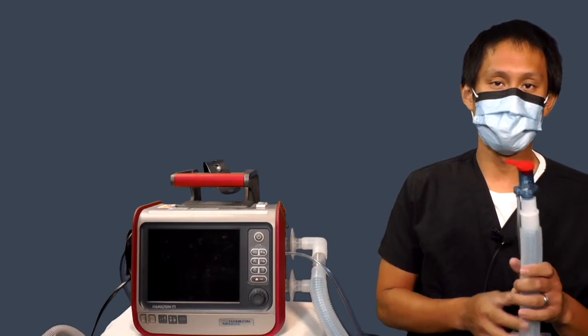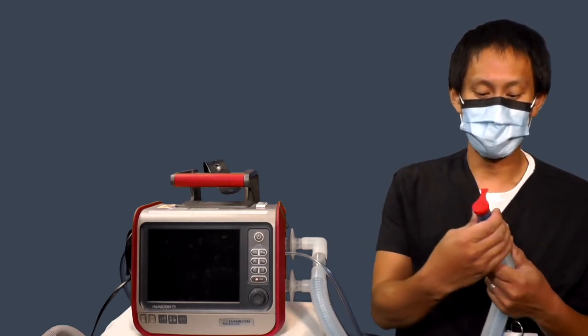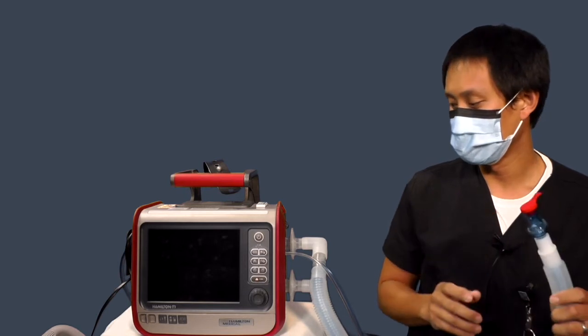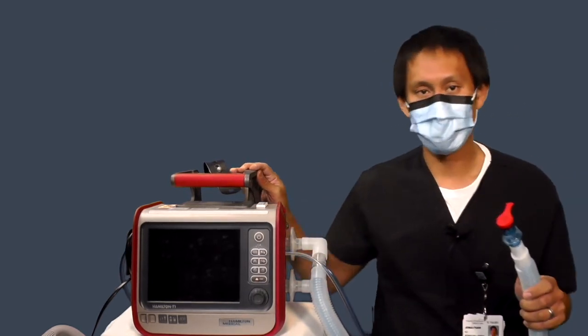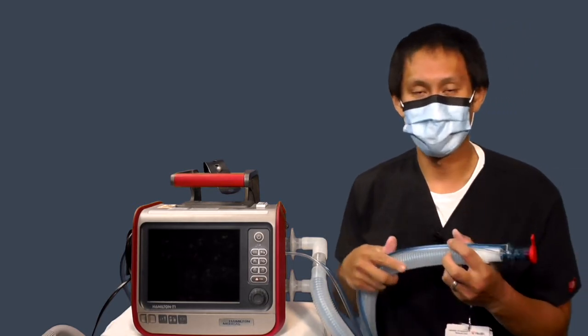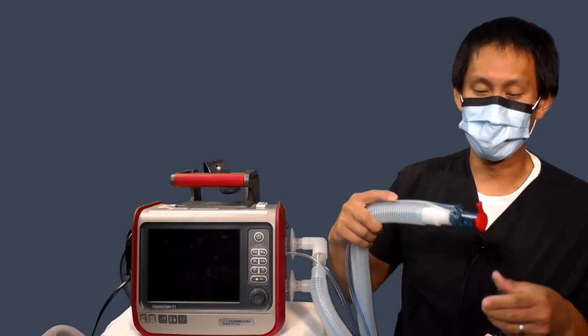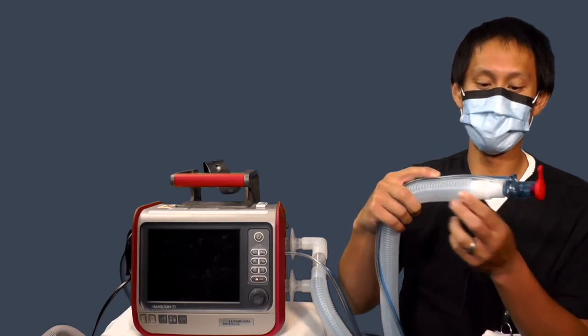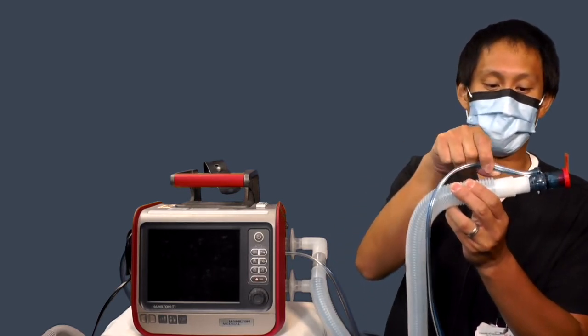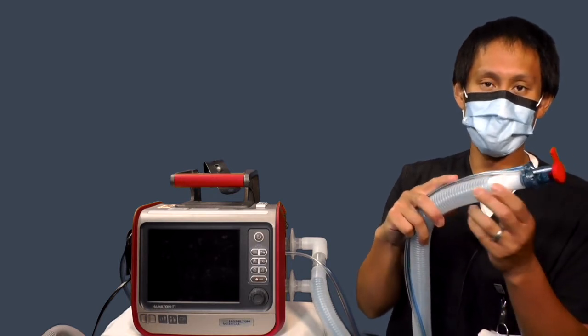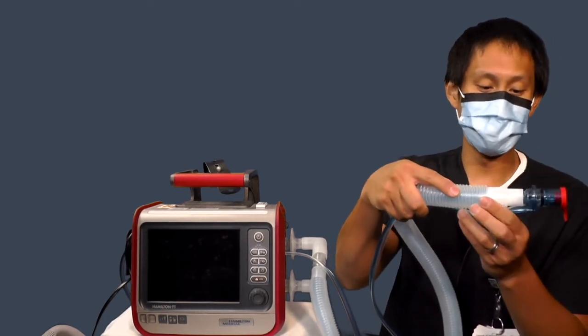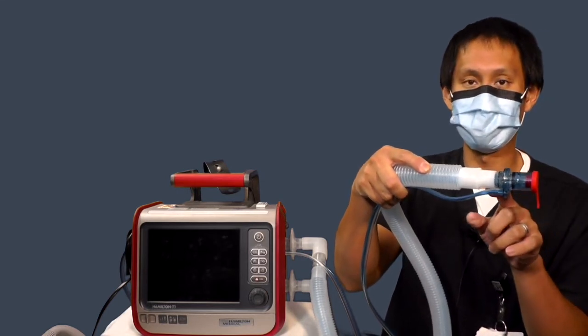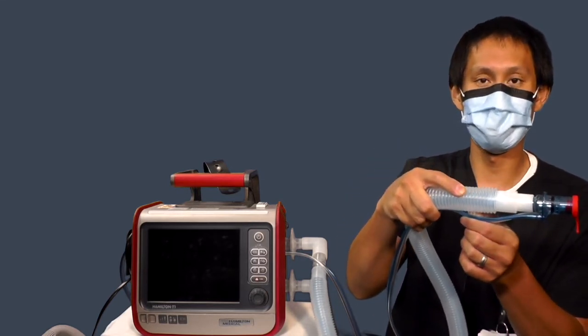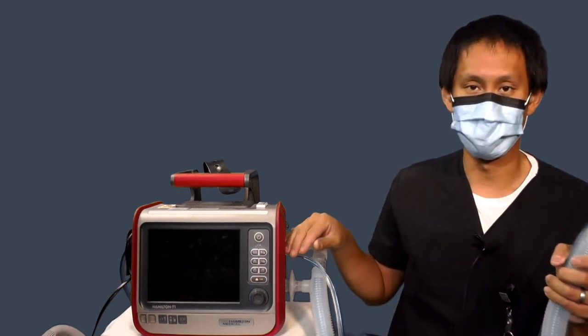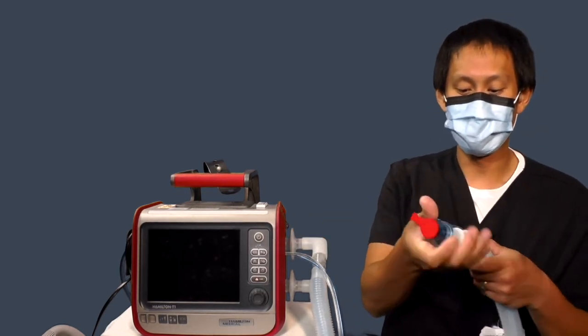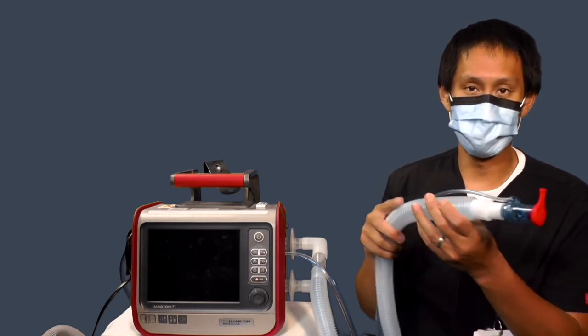Okay, so some troubleshooting tips from someone who's been using the Hamilton system for quite a while now. When you're ventilating a patient, be very cognizant of how you place the flow sensor. You'll notice the two tubes on the flow sensor. You want to try to keep these upright. Otherwise, if you have them inadvertently turned upside down, moisture or condensation can get trapped inside these tubes, and that will render your flow sensor useless. So try to keep this upright so that way gravity is your friend.